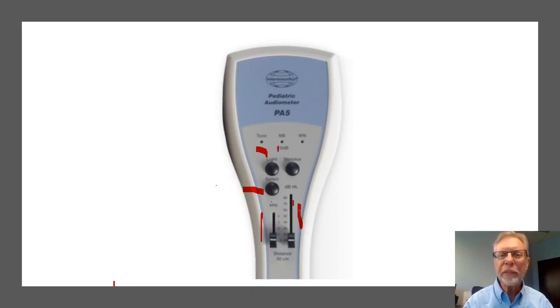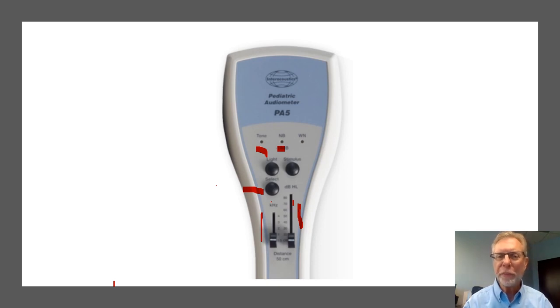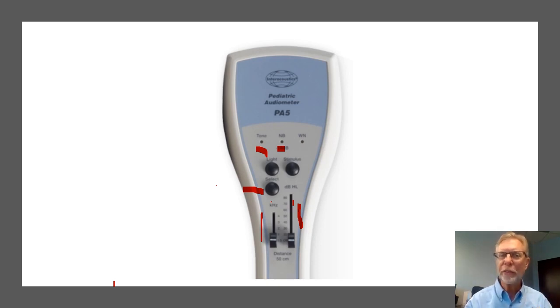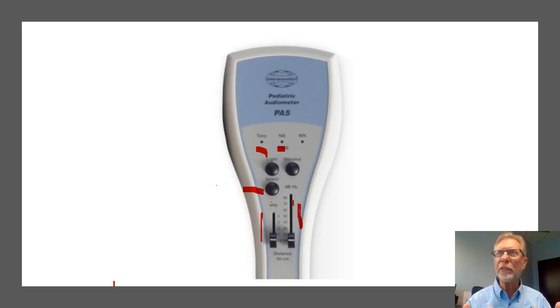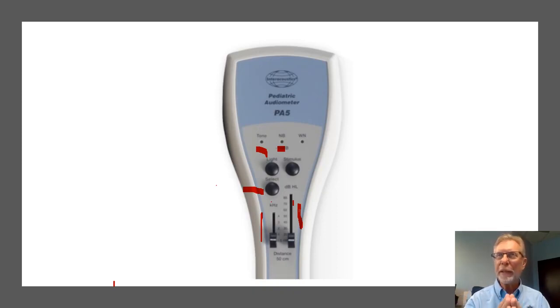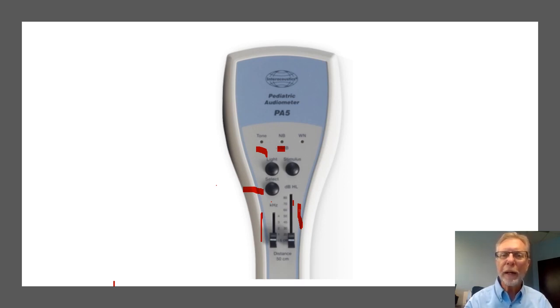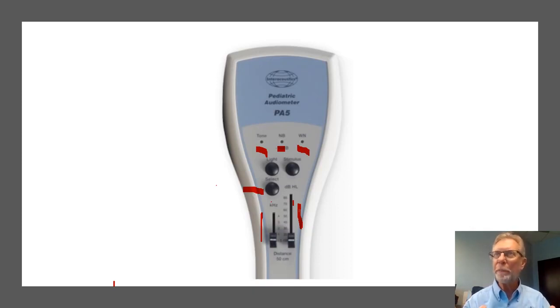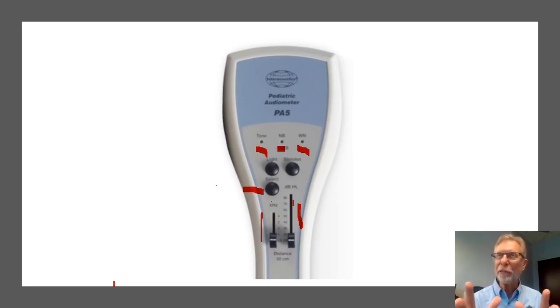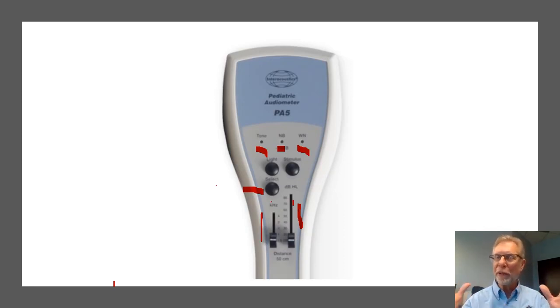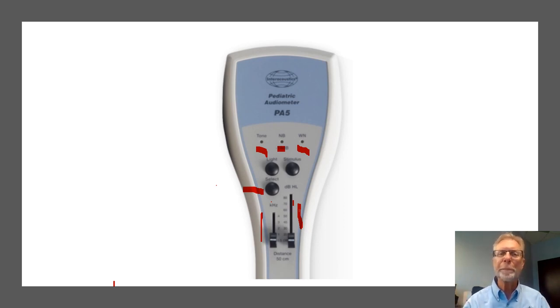This is a narrow band noise, and the frequency of that noise will change as you change the frequency, just like the tones would change their frequency. Narrow band noise is a noise that is centered around the test frequency. And then there is also a selection of white noise. Now, that's broadband noise. It's not frequency specific. It's not a particular frequency. It is just all frequencies, all audible frequencies.